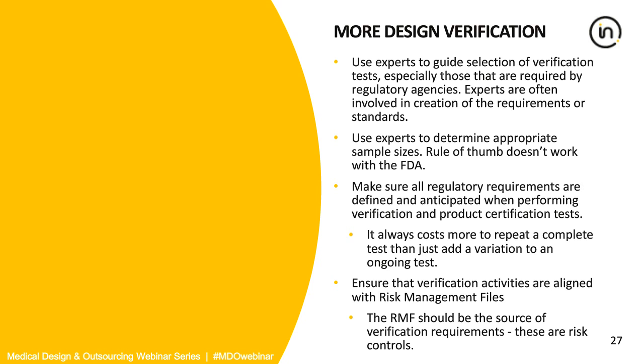So also use experts. If you don't have a statistician in-house, use an expert to determine the appropriate sample sizes, especially for verification testing, because the old rules of thumb don't always work with the FDA. They've got some very smart people there, and they sit down and say, you haven't demonstrated with statistical significance that your product meets your specifications. You need a larger sample size, or you need to do it in a different manner. So get in touch with those statisticians and ask them, can I really make the claim I want to make if I pass my verification testing?